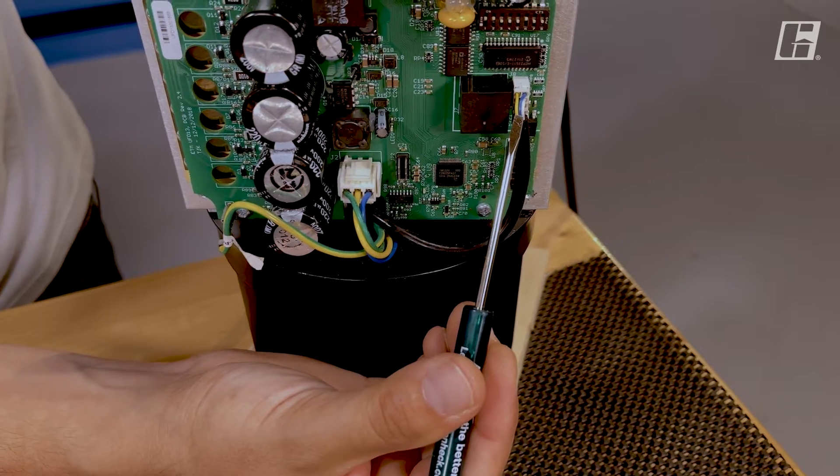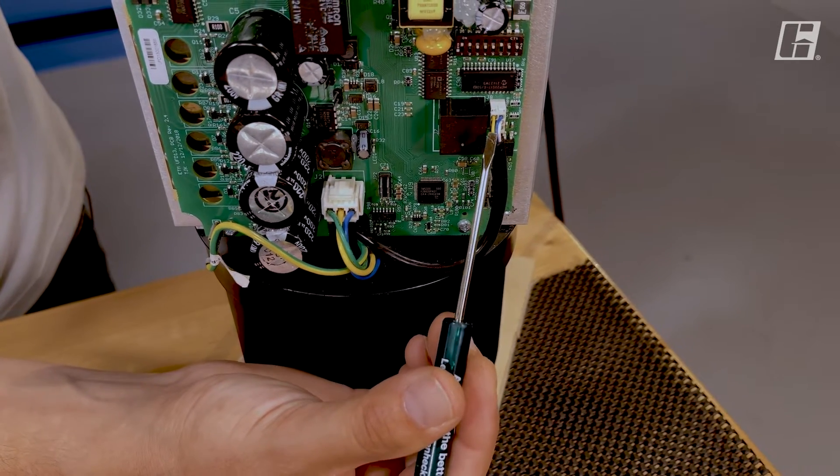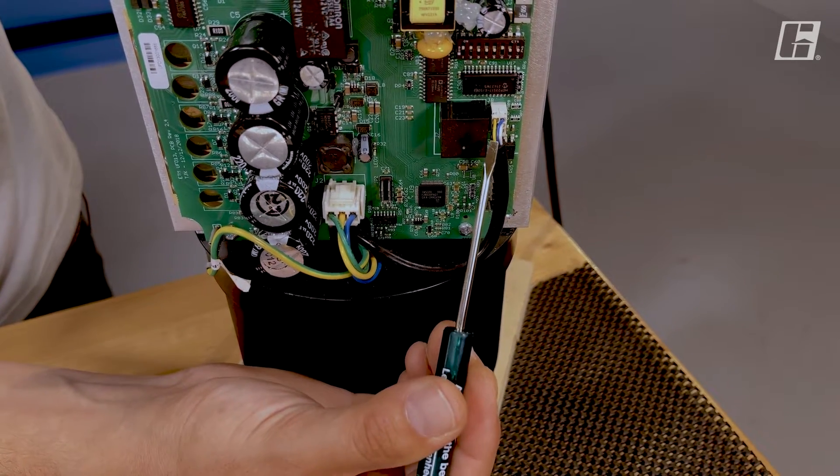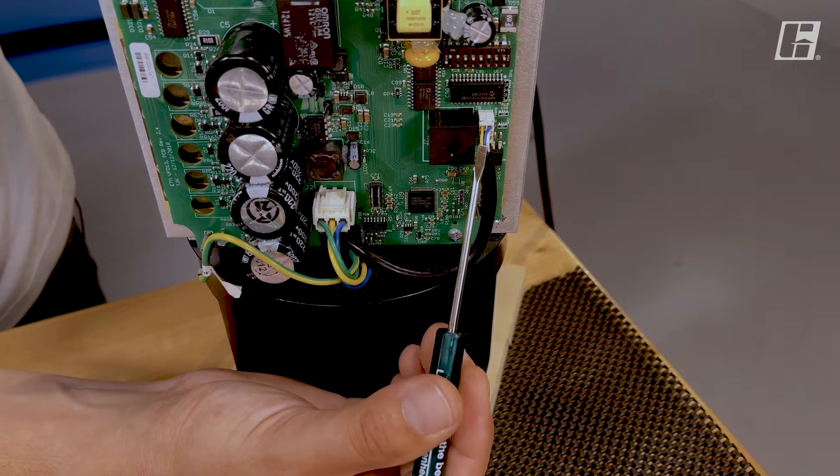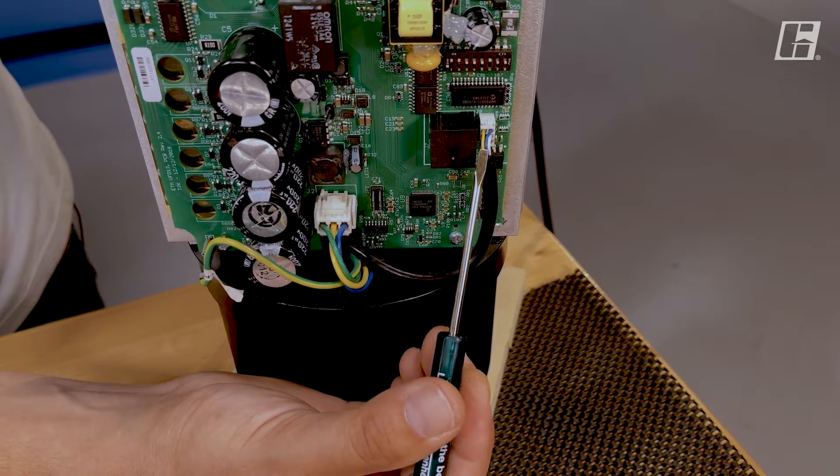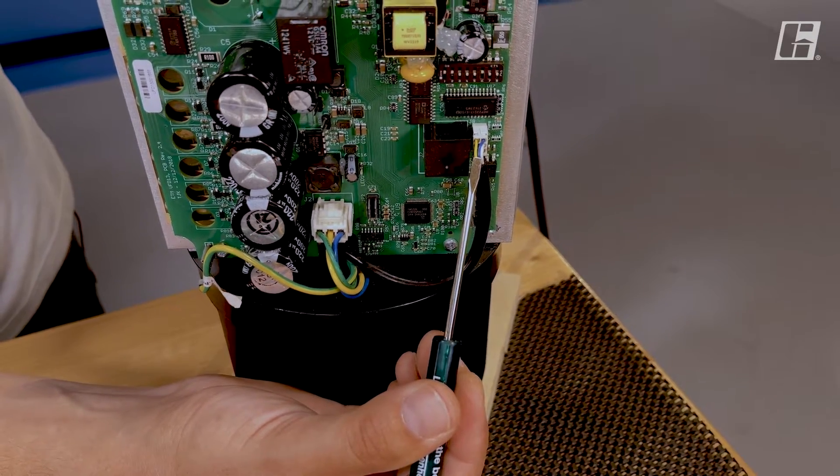The hall effect sensor gives feedback to the drive. If this is plugged in incorrectly, upside down, or not all the way, the motor will stall and think that there's an impact detection because it can't tell the direction that it's rotating.